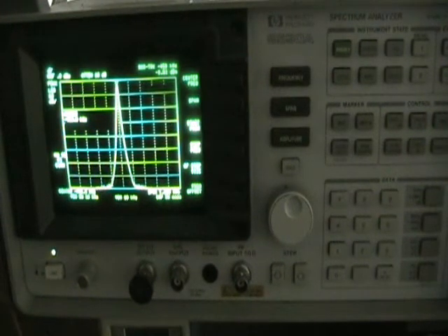We already said that this is a 0 frequency marker. What is up with this? Well, the spectrum analyzer is meant for hundreds of megahertz to gigahertz working. And so the 0 indicator can be off by some amount. This is just a value you must ignore and work with and treat it as 0. Don't count on that value being the same on every spectrum analyzer. It's related to the individual spectrum analyzer, and it will change as the spectrum analyzer heats up. So do not use the zero frequency marker frequency.